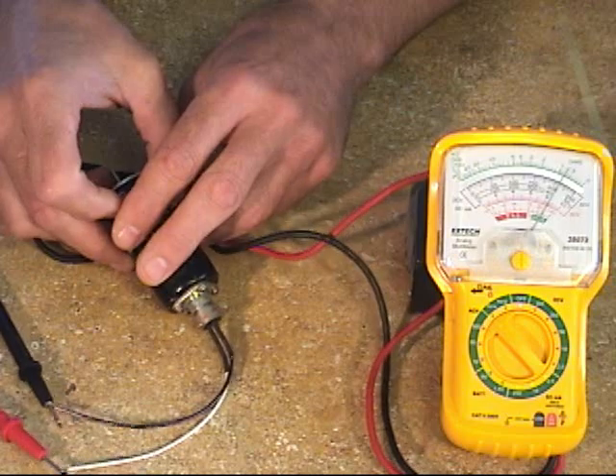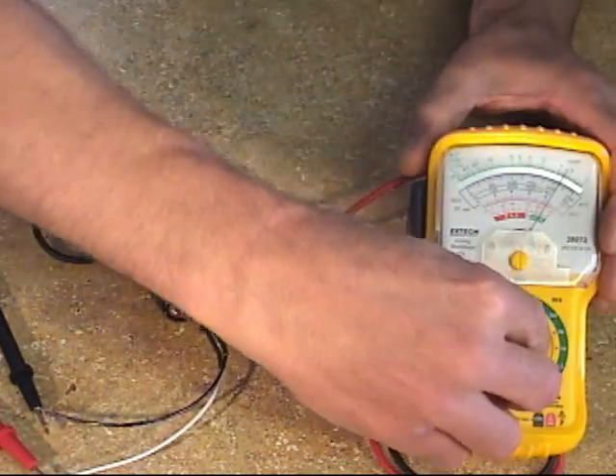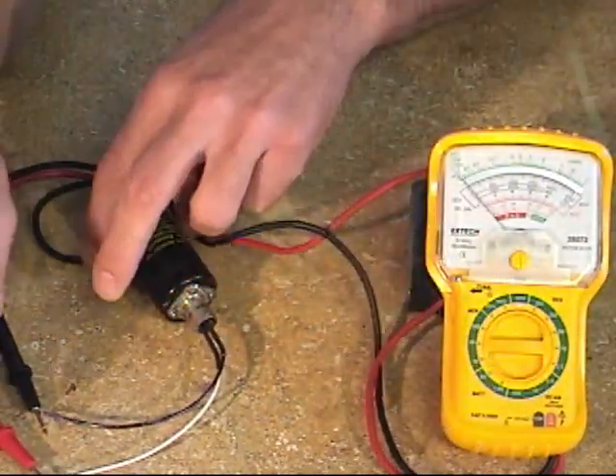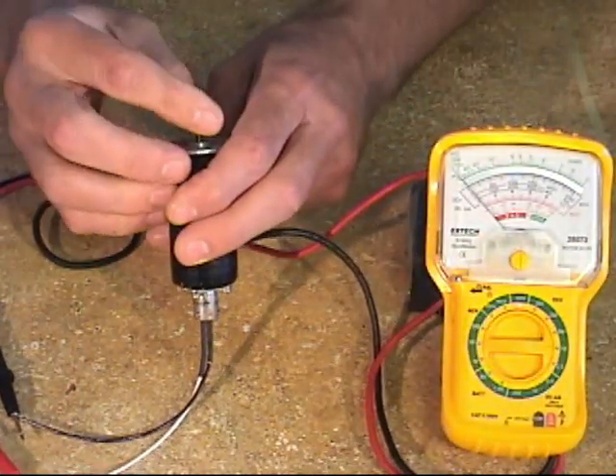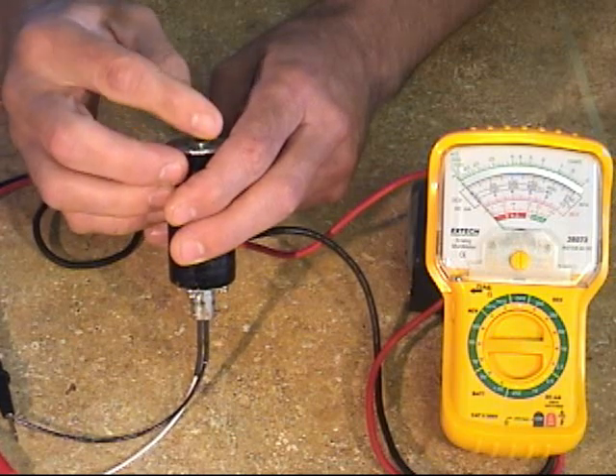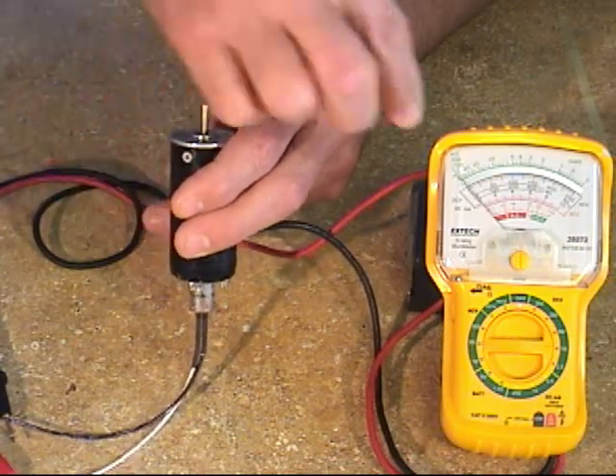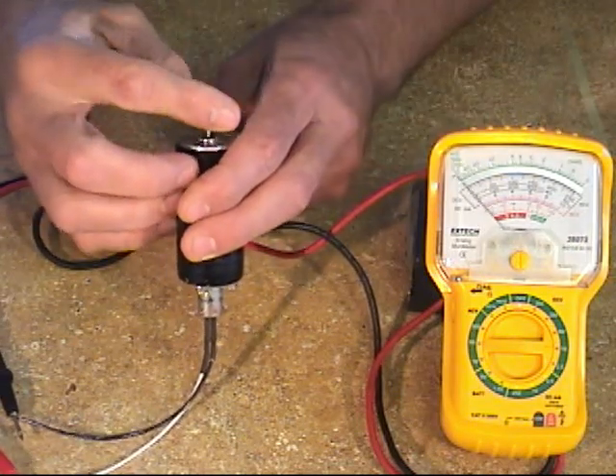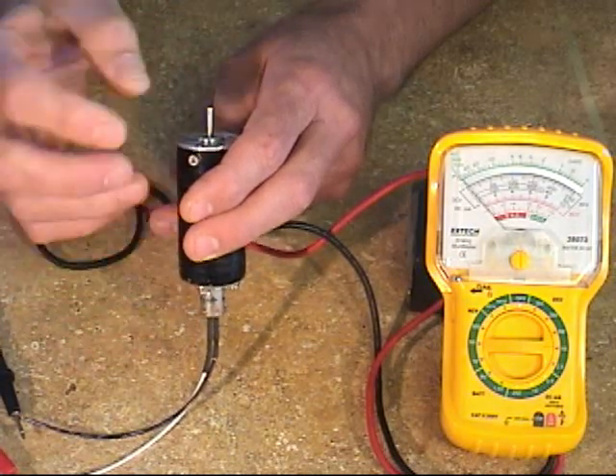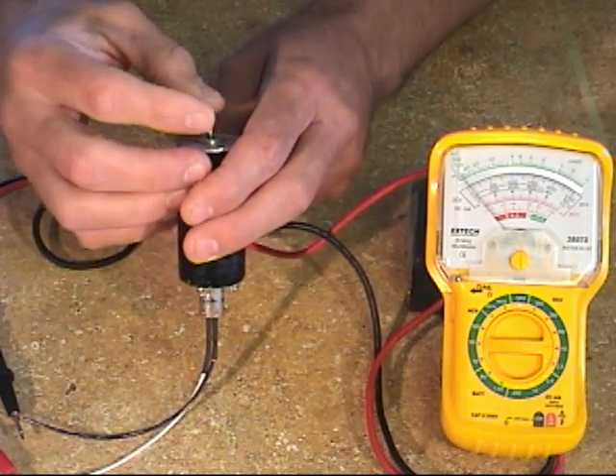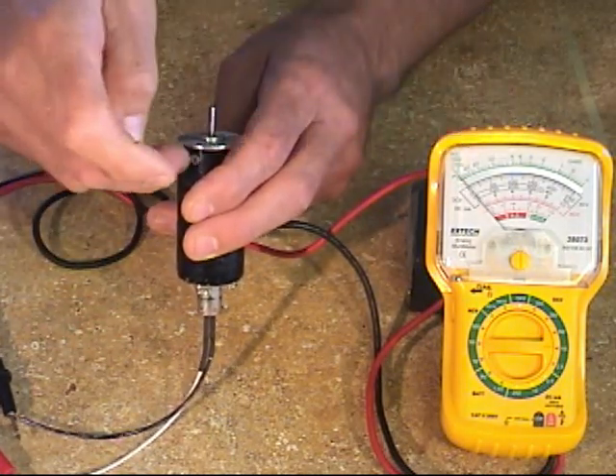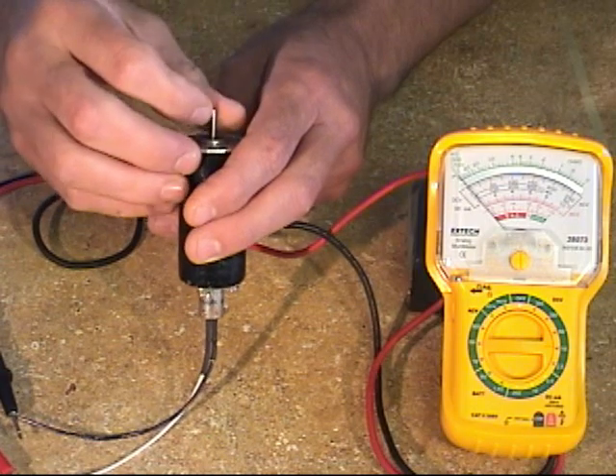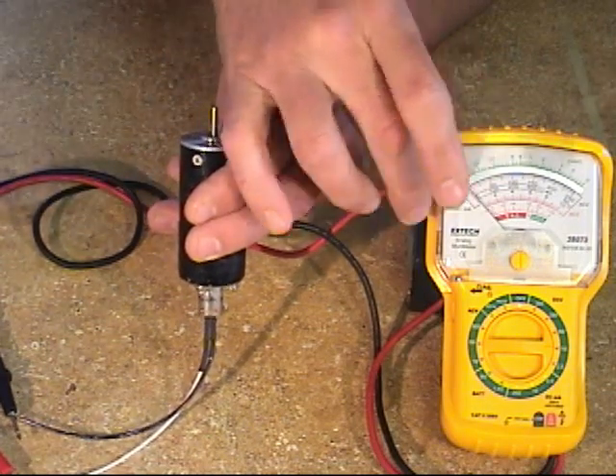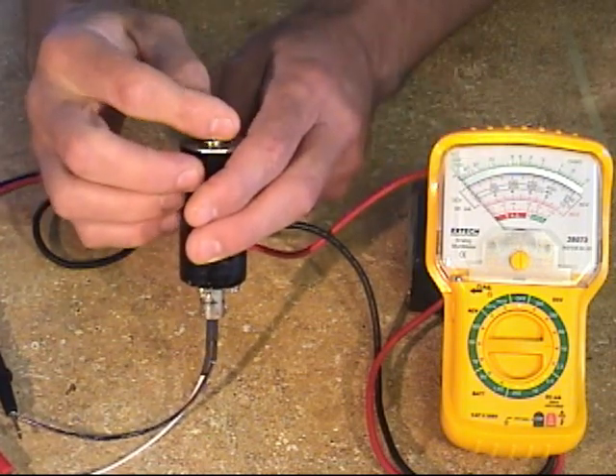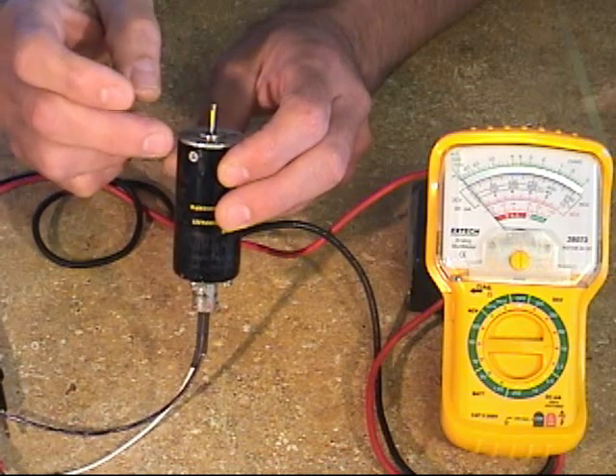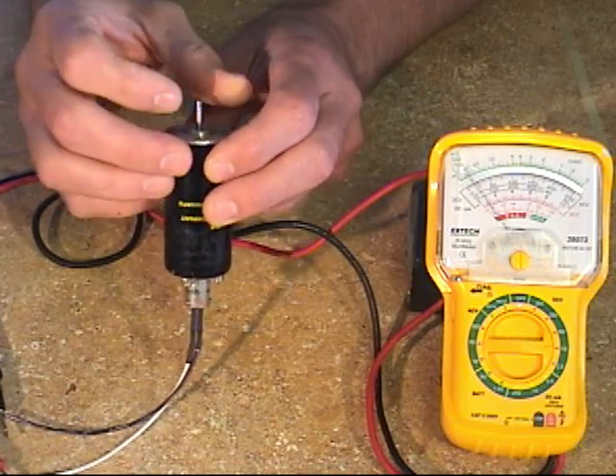Next thing we'll do is leave this analog meter on. We'll turn this to volts. And with this tachometer faced towards your face, turn the shaft clockwise, and the meter should read positive voltage, assuming we've got all our polarity right. What you're watching for is this tachometer to be internally wired backwards, and it might look like that, driving the needle back the wrong direction. That would be a transducer wired incorrectly internally.